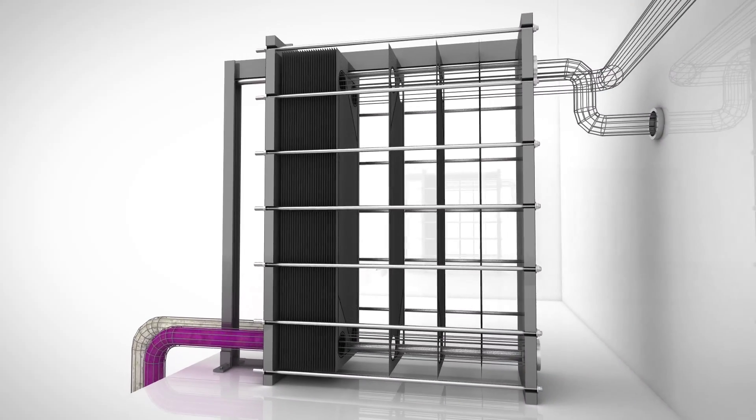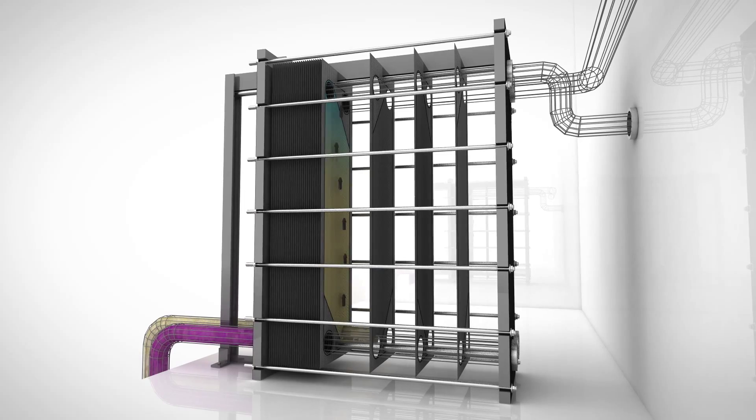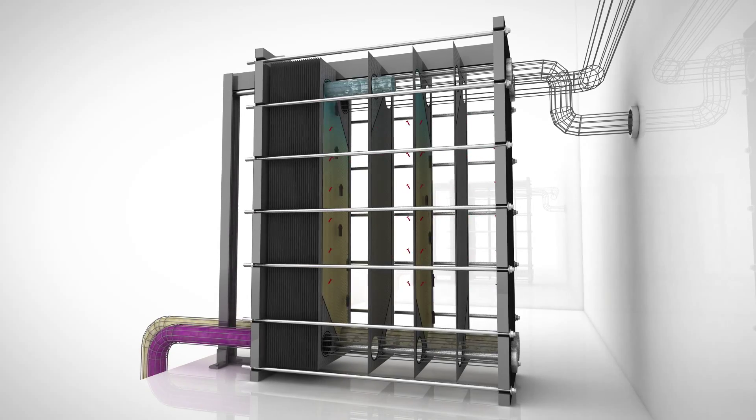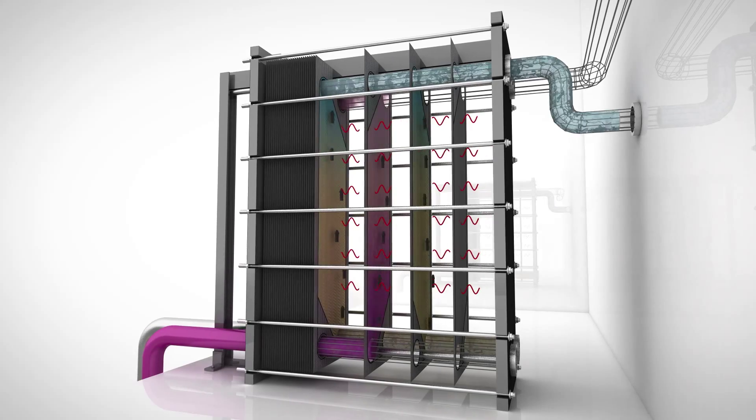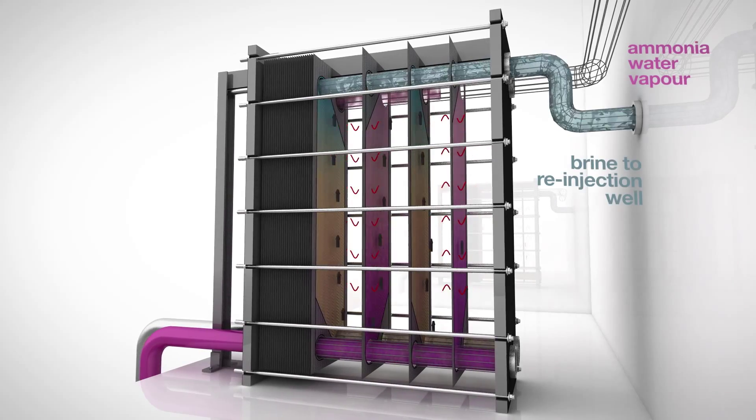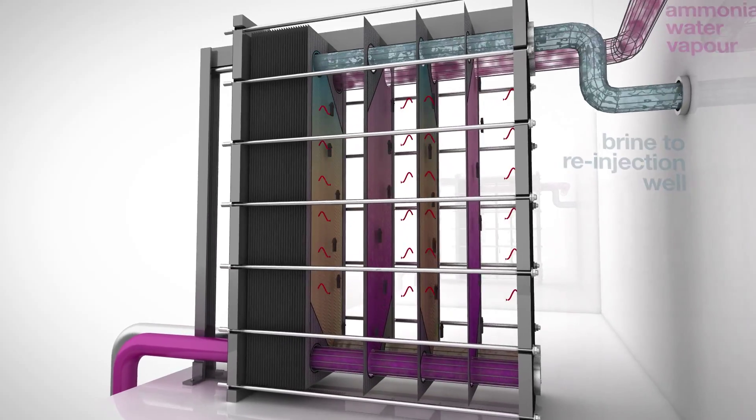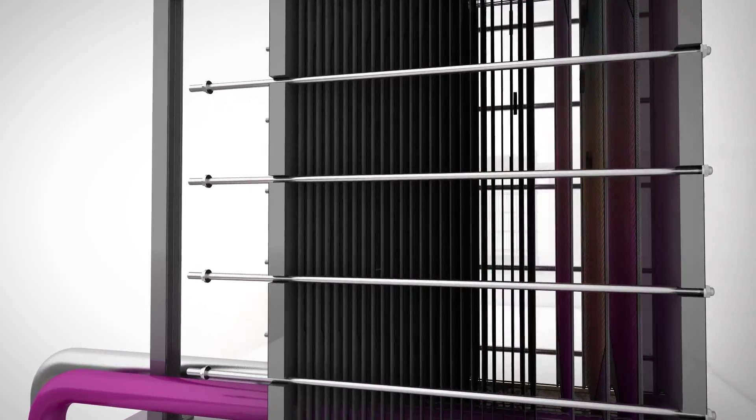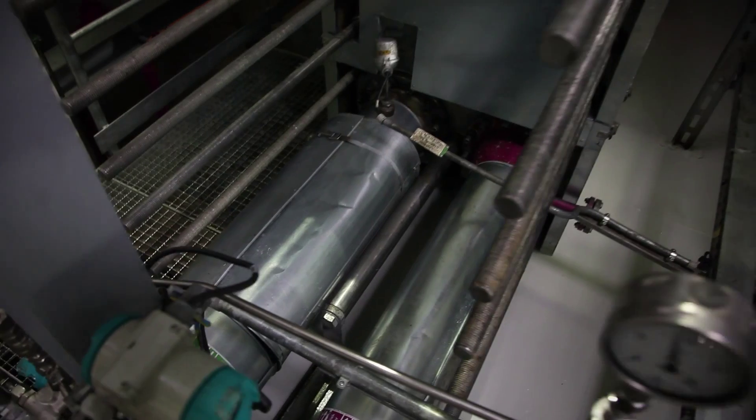Inside the evaporator, the geothermal brine flows between a series of plates. A mixture of pure ammonia and water is also flowing through a series of plates alternating with the brine. The ammonia-water mixture and geothermal brine flow on opposite sides of the plates to exchange heat through the plates. Without ever contacting or mixing with the brine, the ammonia-water receives heat from the brine and begins to boil. At this point, the brine has done its work and can be returned to the earth for reheating through the injection well.